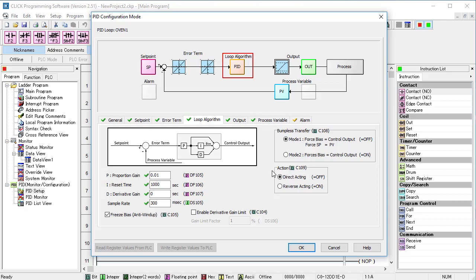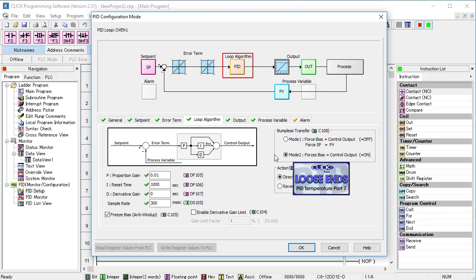Once the system is running in auto, you can then carefully raise the setpoint to whatever value you want. But we want to tune our system for a specific setpoint – we don't want it to move – so we need to choose Bumpless mode 2 which turns that feature off and leaves the setpoint right where we put it. Both modes reset the bias term, which we'll talk more about in the loose ends video.